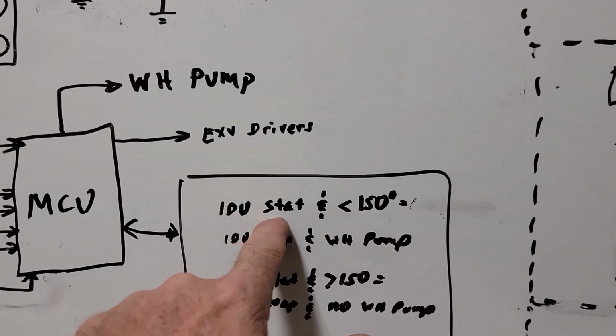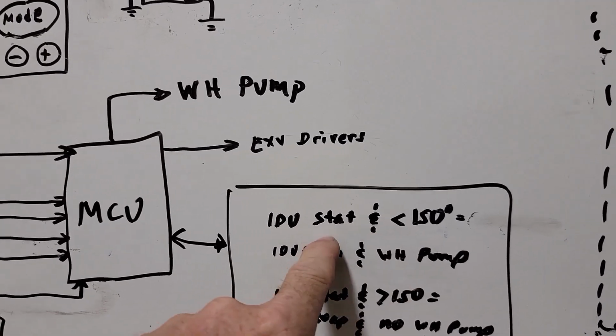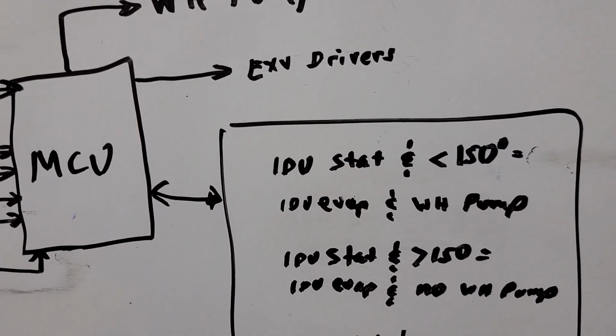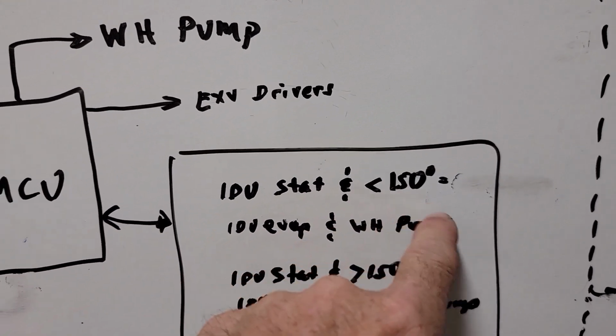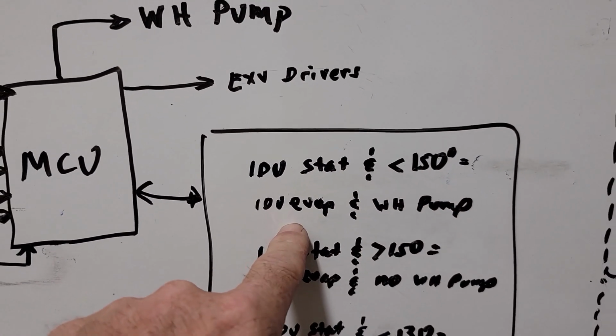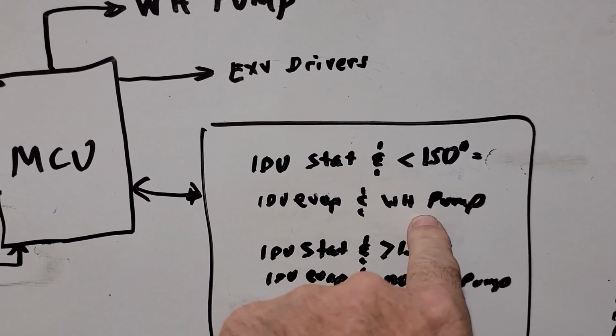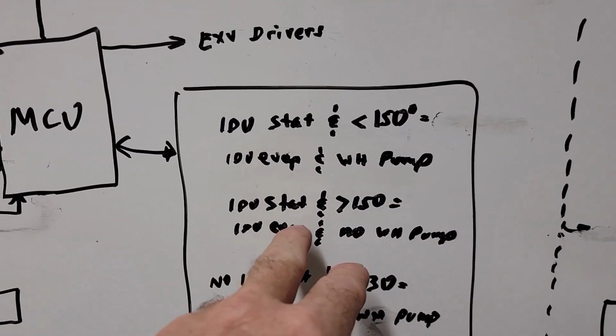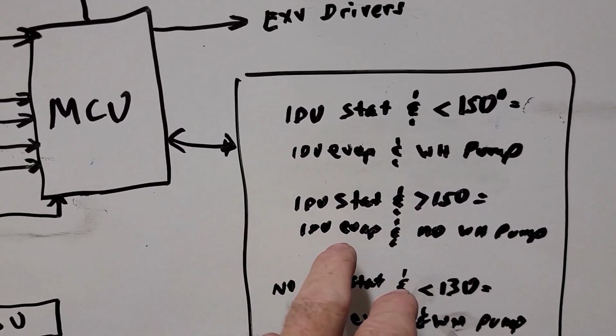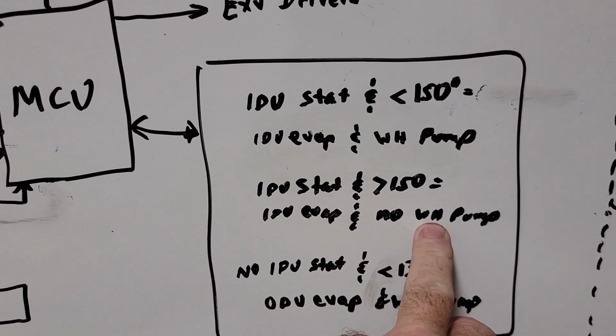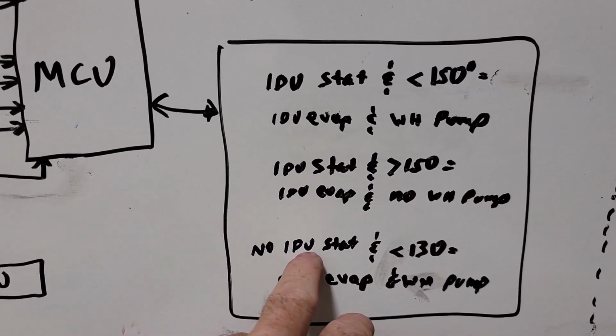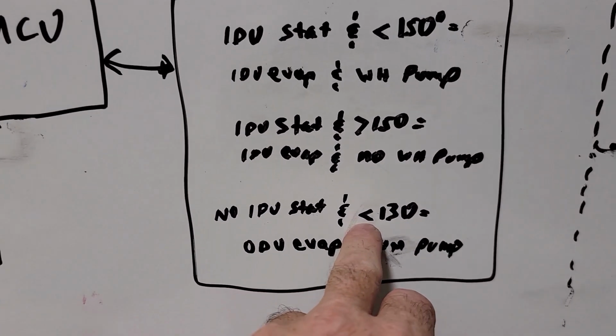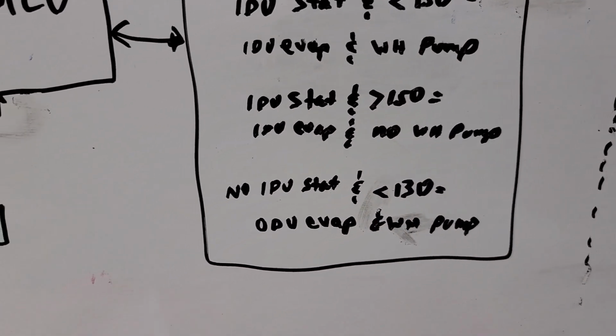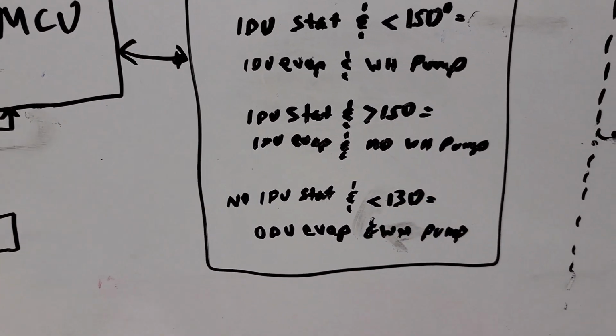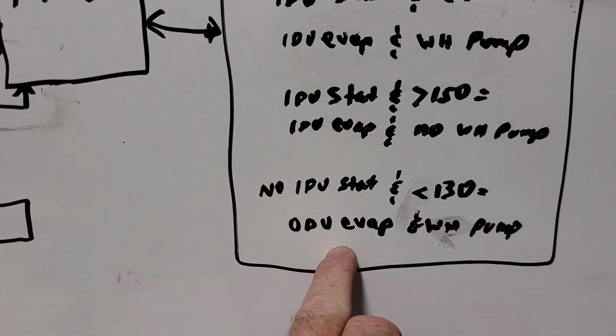So: indoor stat calling for cooling, and less than 150 in the water heater, equals the indoor evap and the water heater pump both running. Indoor stat calling, but over 150 degrees, means the indoor evap runs with no water pump. If there's no indoor stat call and it's below 130 (with the differential, that's my cutout), then it's outdoor evap and water.